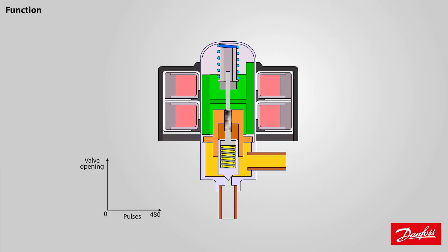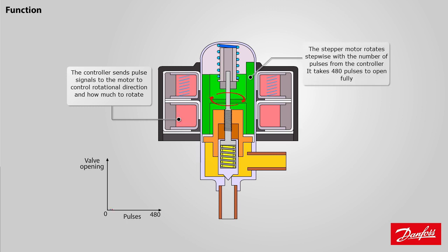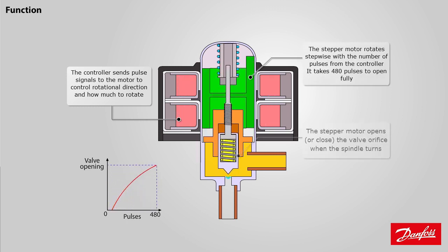But in case of high superheat, it means that refrigerant leaving the evaporator is vaporized more than it should be. It can result in high compressor operating and discharge temperature and low cooling efficiency. To maintain the required flow, the EEV will respond by opening to allow more refrigerant into the evaporator to meet the desired temperature.